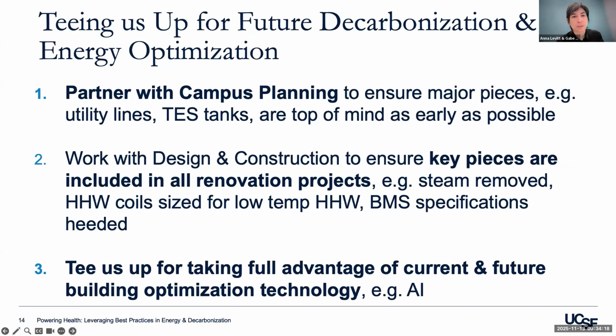We're also working with design and construction to ensure key pieces are included in all renovation projects. Any construction in a hospital is incredibly disruptive since we're trying to do patient care 24/7, so wherever we can include advancement of decarbonization in an existing renovation project, we make sure that's happening — removing steam dependence, sizing heating hot water coils for low temp heating hot water, and making sure our building management system specifications are updated.